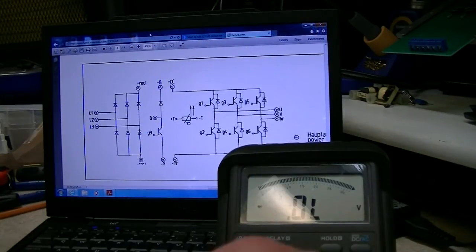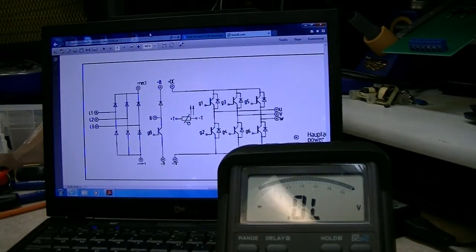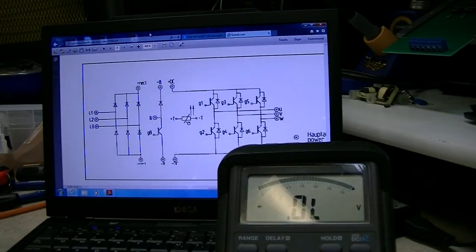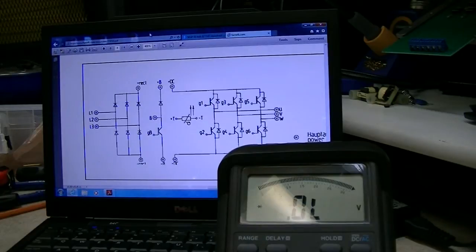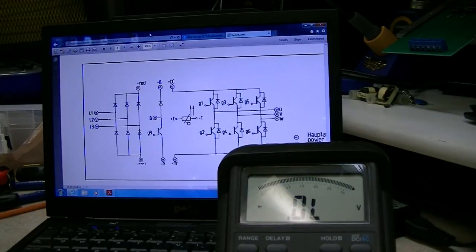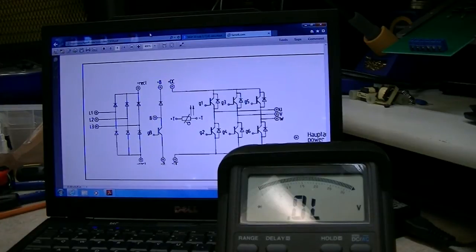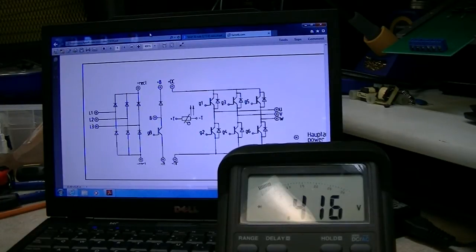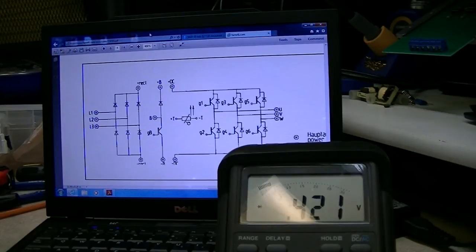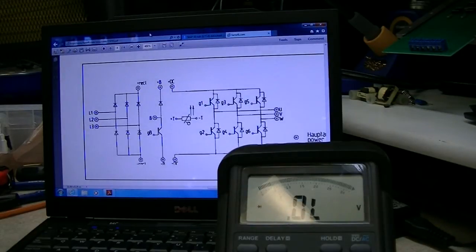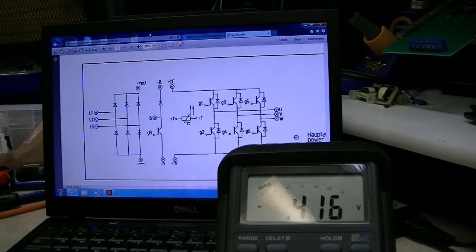And we'll see what we get just with the meter itself. So let me find here rectifier 2, okay, L1, L2, L3, okay, good that way. Swap the leads. L1, okay, there's a diode drop, 416, 421 at L2, 421 at L3. This is slightly lower, but it probably doesn't really matter.